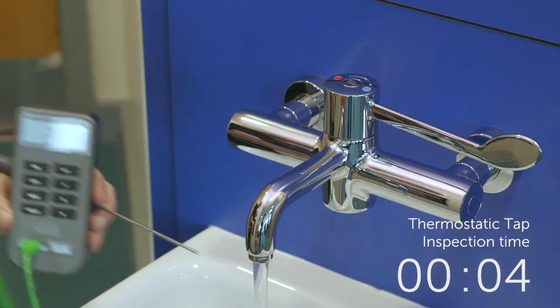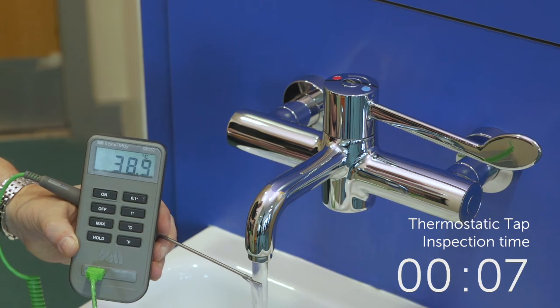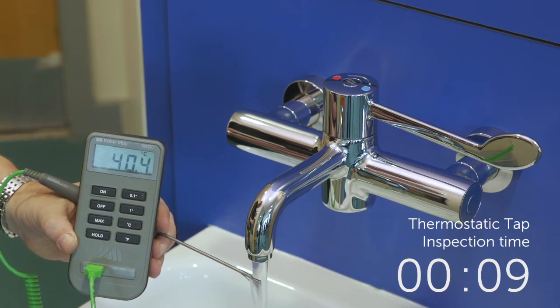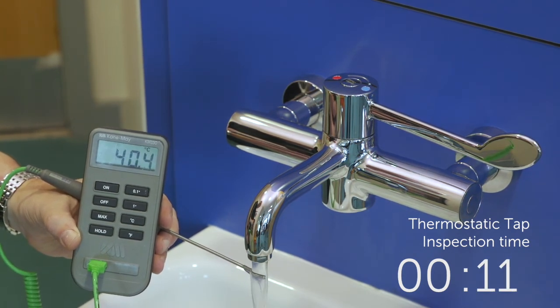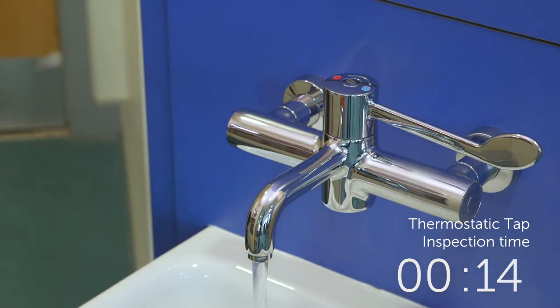The testing procedure outlined in HTM 0401 now takes just over a minute to complete on the Markquik 21 Plus tap, and only has to be conducted every 12 months after three successful tests.